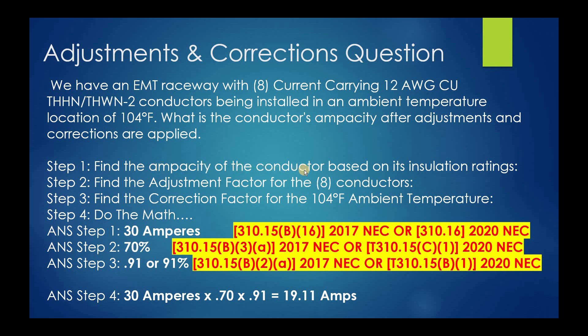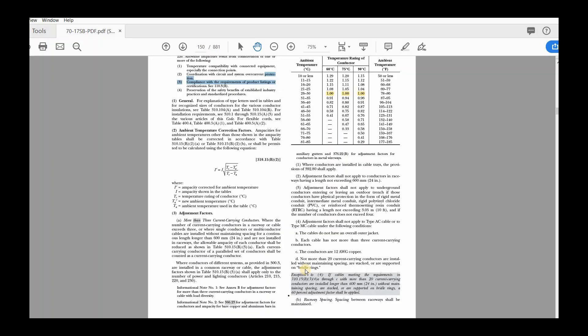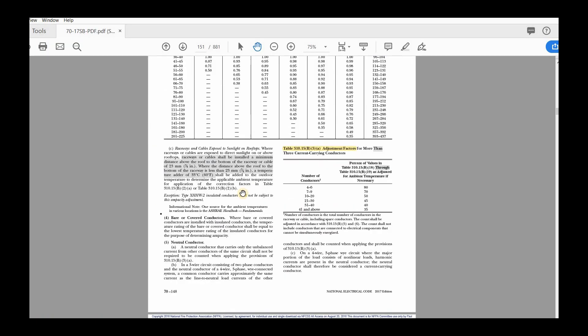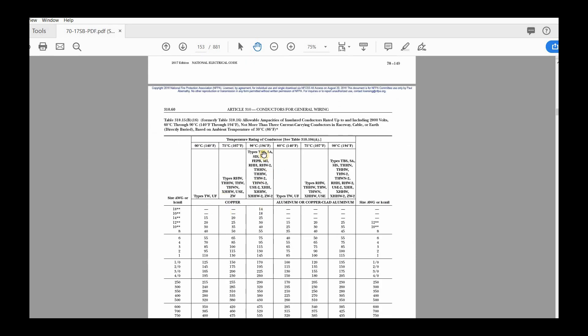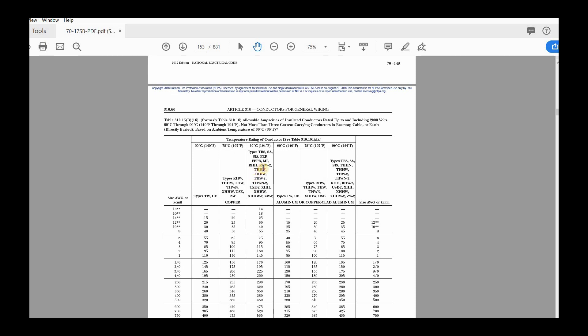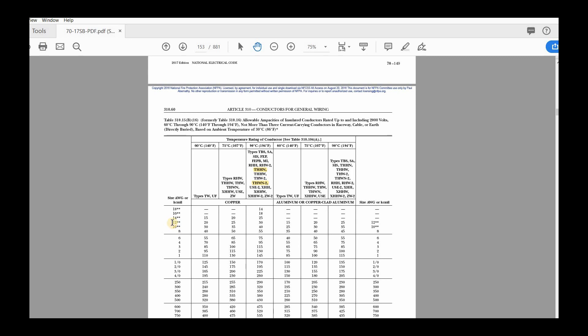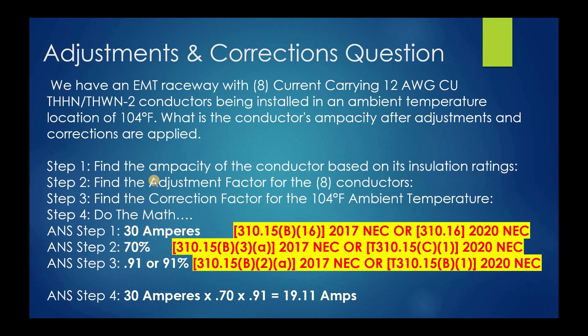The first thing we're going to do is find the ampacity for the insulation rating — THHN/THWN-2. So let's go to the code. As you can see, I'm going to go down to the ampacity table right here. THHN is listed here, as well as THWN-2 right here. We're looking for 12 gauge, and we come over here — it is 30 amperes. So that's what we have to work with. That was step one: 30 amperes.